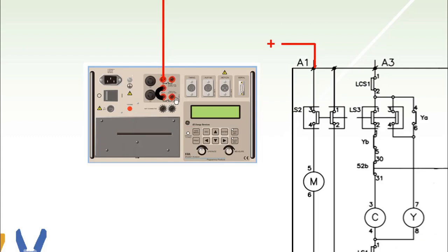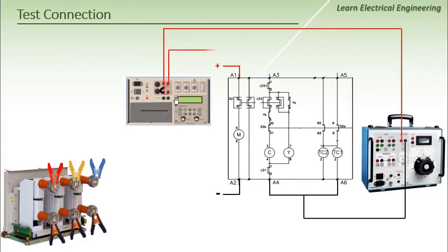And I will take the terminal labeled close coil and connect it to the positive terminal of the close coil, and take the terminal labeled trip coil and connect it to the positive terminal of the trip coil. This way, I have completed my control circuit.